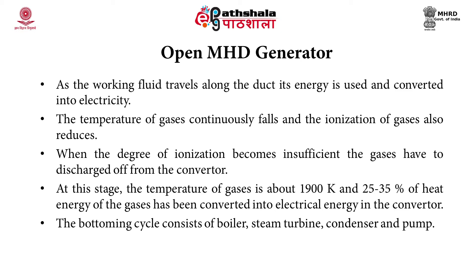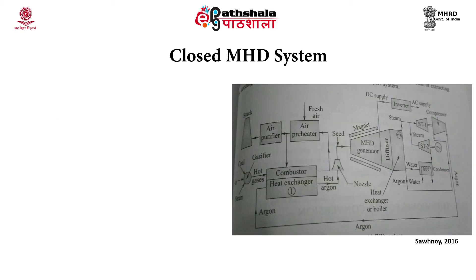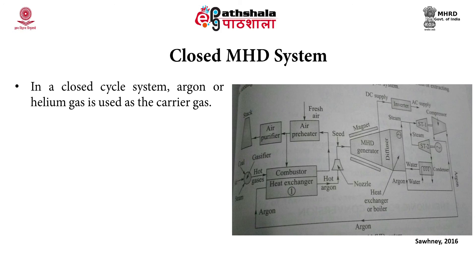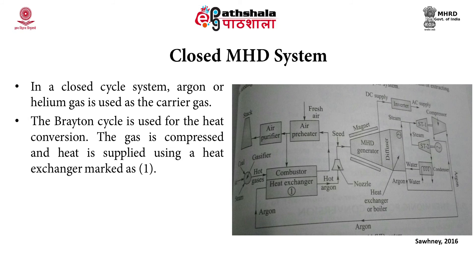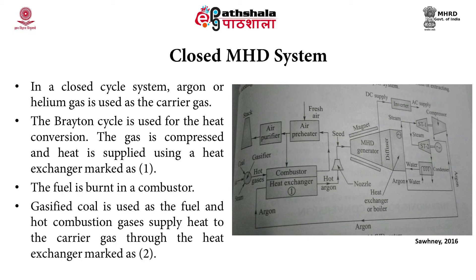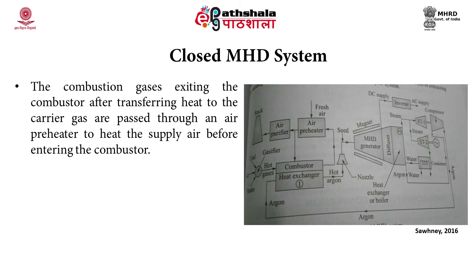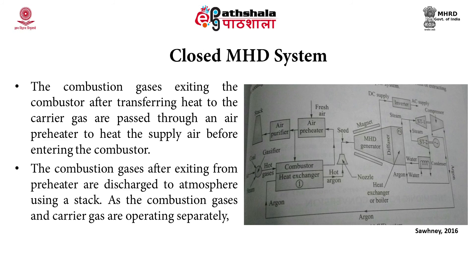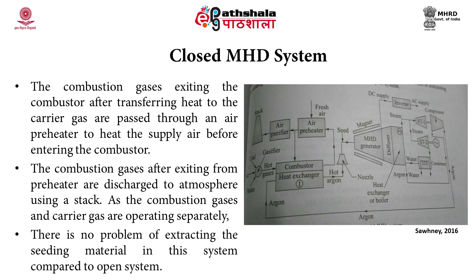The steam generated is used in a steam turbine with a directly coupled generator, which converts 25–30% of the total heat into electric power. The gases exiting the boiler are passed through a seeding material removal device before being discharged to the atmosphere through a stack. The bottoming cycle consists of a boiler, steam turbine, condenser, and pump. In the closed cycle system, argon or helium gas is used as the carrier gas. The gas is compressed and heat is supplied using a heat exchanger. Combustion gases supply heat to the carrier gas through a secondary heat exchanger, and after transferring heat, are passed through an air preheater before being discharged to atmosphere. Since combustion gases and carrier gas operate separately, there is no problem of extracting seeding material, unlike the open cycle system.